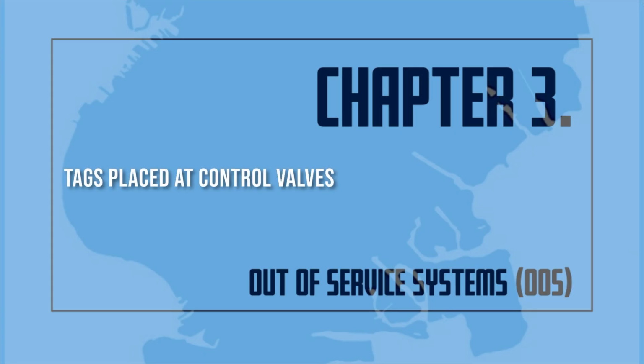Tags placed at control valves shall indicate the level of impairment or defect as follows. System fully or majorly out of service: red tag, white disc. System is found with critical deficiency: orange tag, blue disc. System is found with non-critical deficiencies: yellow tag, blue disc. System appears free of defects or deficiencies: green tag, no disc. Only the fire department, the owner, a master fire suppression piping contractor, or a master licensed plumber, as restricted, may place a tag on a system.